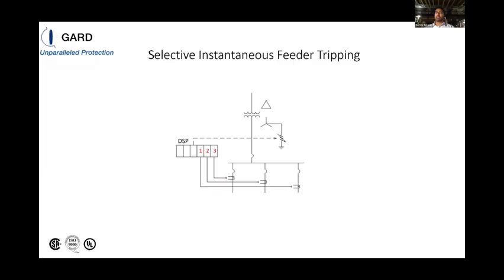So for selective instantaneous feeder tripping, let's say, for example, we're experiencing a fault on feeder 1, phase A. That fault is now being limited by this NGR, and we haven't tripped this fault open. Our DSP system is monitoring the resistor as well as all 3 feeders. When another fault occurs on another feeder on another phase, these faults are now going to be circulating between each other, and the neutral grounding resistor is out of the game. It cannot limit the fault current to a specific value because now we're experiencing a phase-to-phase failure, and the current between these 2 points is building up.